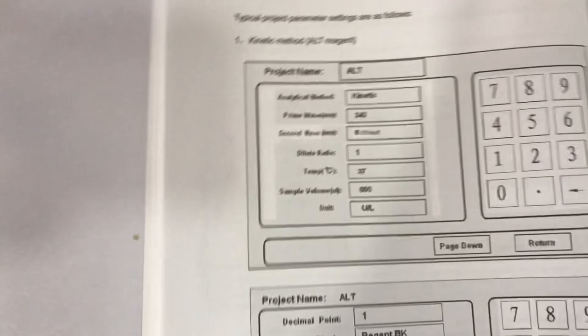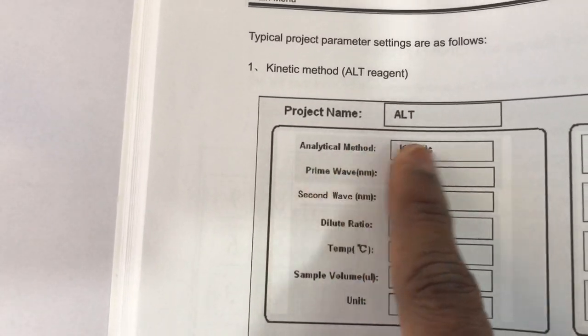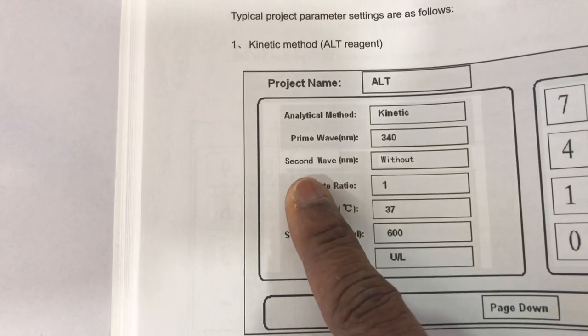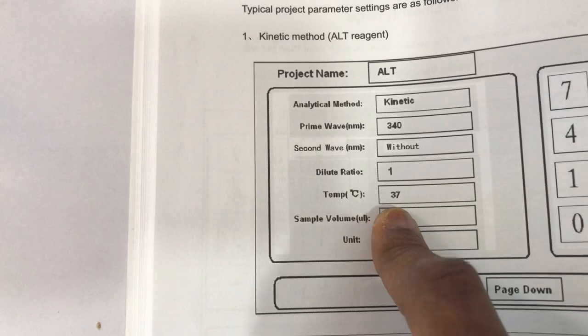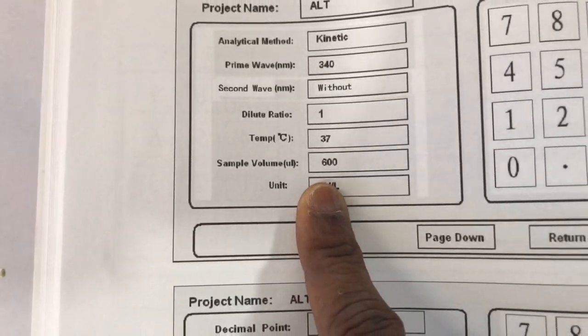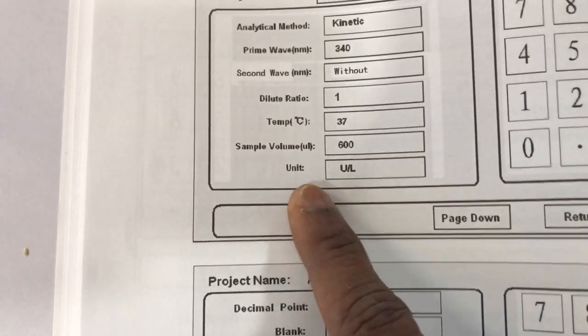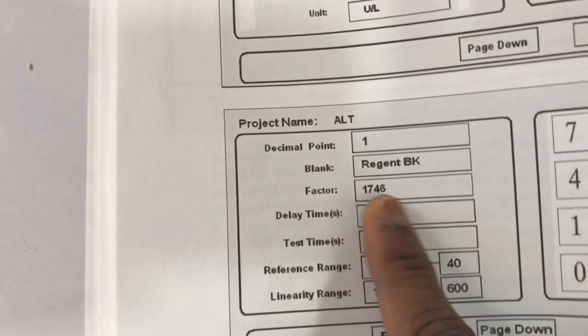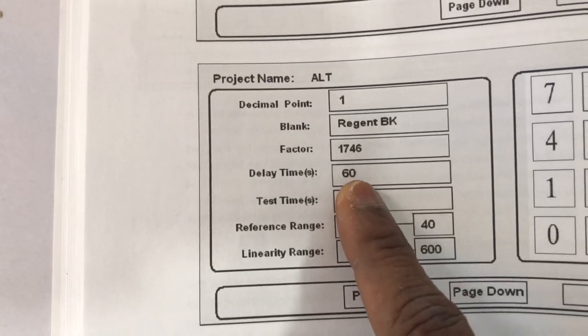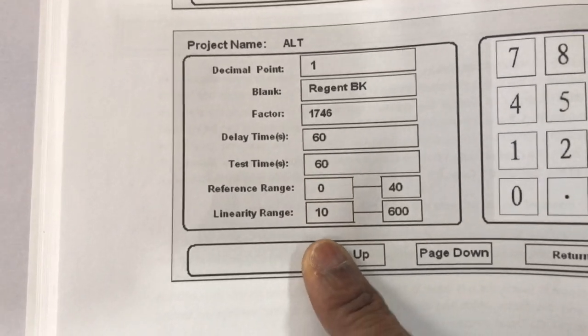Now let's look at a kinetic method — for example, ALT. The analytical method is kinetic. The primary wavelength is 340 nm; no secondary wavelength is needed. Dilution is set to one. Temperature is 37 degrees Celsius — always follow the manufacturer's instructions. Sample volume is 600 microliters. The unit is international units per liter. Set the decimal point to one, do a reagent blank, and the manufacturer provides the factor: 1746 for this assay. The delay time is 60 seconds and the test time is 60 seconds.